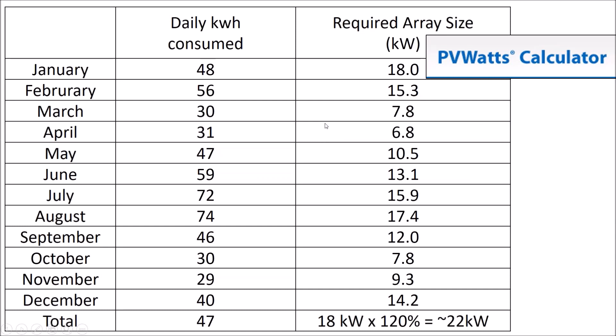So on these float, absorb, bulk charts, the way that you read them is you take how much energy you expect to consume on a daily basis. What I would do is take the storage capacity of the battery bank and then subtract out each day. If I have a 120 kilowatt hour battery bank, and each day I'm discharging it with 48 kilowatt hours, and then charging it with around 48 kilowatt hours all the way back up to the top, there's actually a way to map that out, and we'll show you that in a minute.